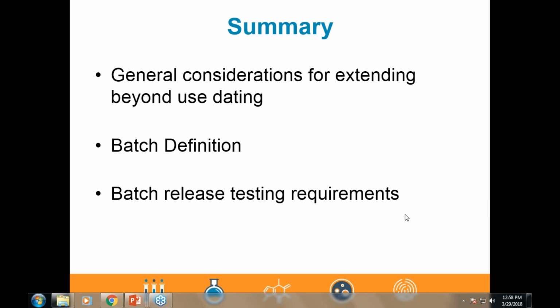The problematic thing sometimes for small batch sizes is part of the benefit of the container closure integrity test is that you can test a higher number of actual containers as opposed to sterility. That helps, again, provide you a higher level of assurance, which is what FDA is looking for in that case. And a lot of times on the smaller batch sizes, it's difficult to do that. But yes, there is an actual guidance out there by FDA where it talks about doing container closure integrity in lieu of the sterility test.